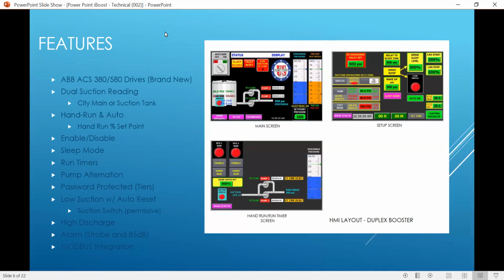As far as our key features and the touchscreen, we're using a Siemens touchscreen. These are your three basic screens for the booster. You've got your main screen on the left-hand side here, and this is showing you, with a tank suction, basically your controls for auto or running in hand. And then right here, in that blue section, it shows your pressure that you're running at. And then this is your PID loop screen right here.